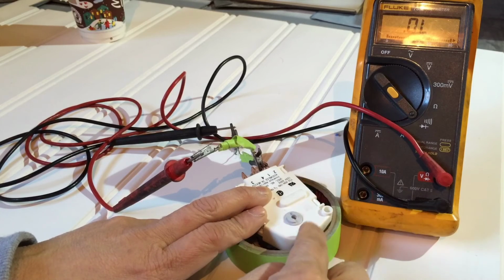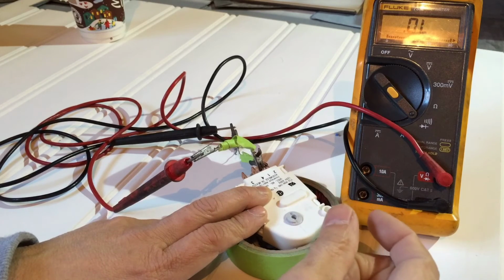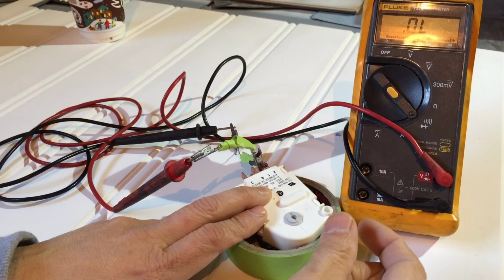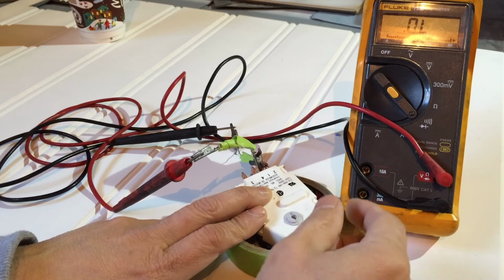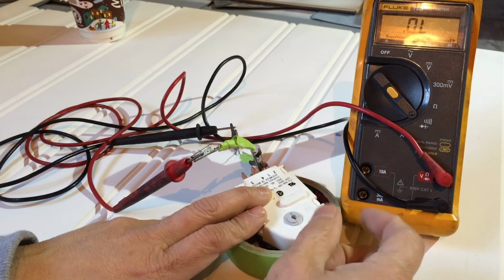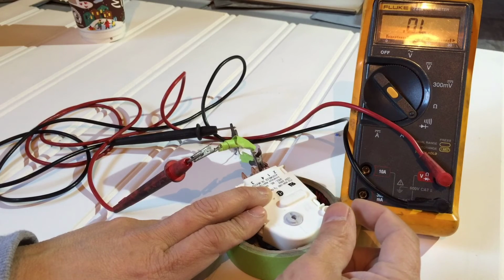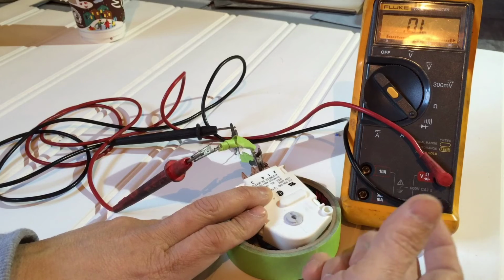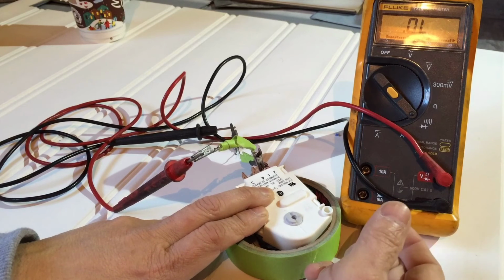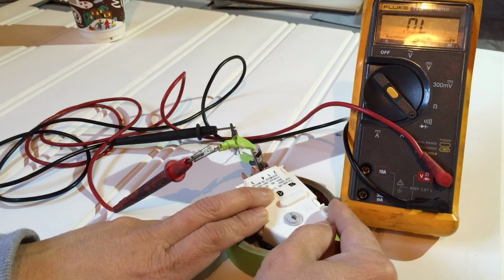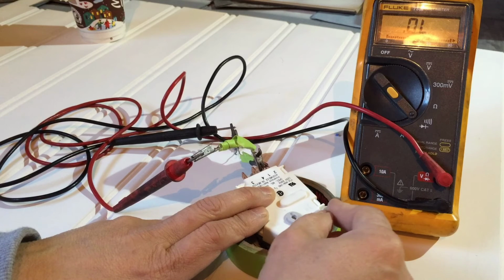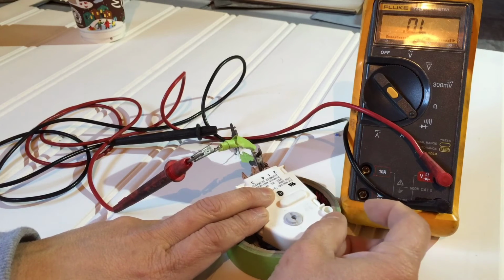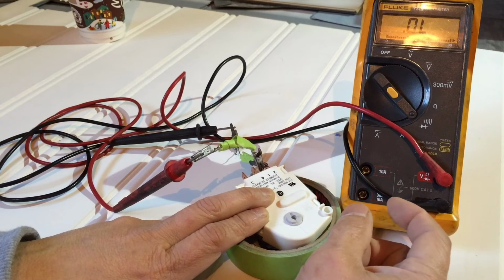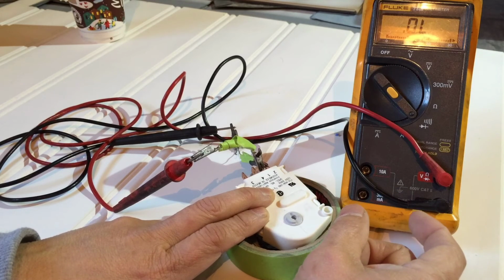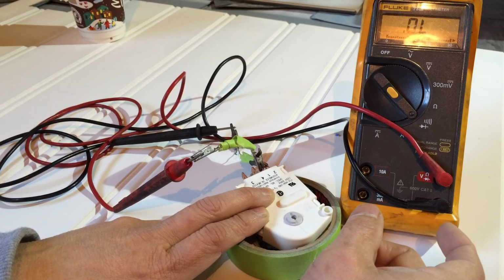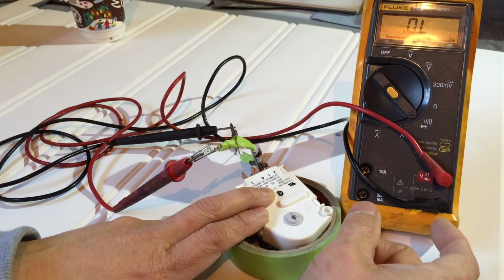In conjunction with the defrost timer, there is a bimetal switch attached, as you can see in the photo, circled in yellow. The bimetal switch makes or breaks the connection depending on whether the fridge needs to be defrosted. That switch works when it's cold: when cold, it makes the connection; when not cold, it doesn't need the defrost cycle, so it stays open.